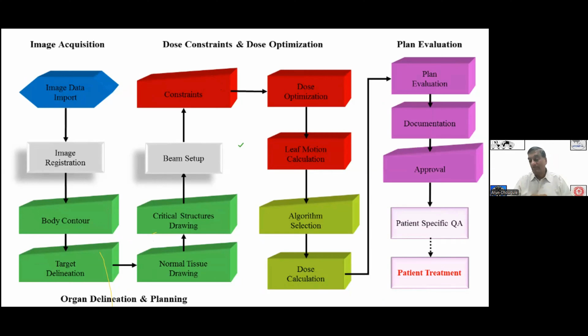This is all. Now, for any radiotherapy or radiation department you are going to plan, I told you about time, dose, and shielding. So shielding, structural shielding, because the harmful effect of radiation is well established. The medical physicist is involved in planning, shielding calculation, and adequate radiation shielding of wards, rooms, and housing for radiotherapy or any other radiation equipment sources, which need to be provided so that radiation exposure to members of the public is kept below the dose limit.